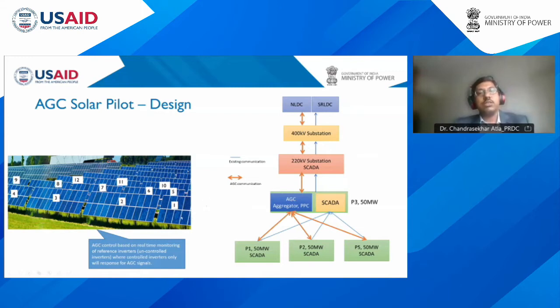the philosophy we made here is by imagining that each solar panel is connected to a 1 megawatt inverter. So identify the inverters in each block and make a couple of inverters reference inverters, maybe 10-20% of the inverters as reference. That means you are not going to control those inverters; those will act as a reference. The remaining inverters you can control, so that you can quantify how the inverters are responding. Basically in regulation down, especially in critical cases, if you operate the plant lower than the availability, then you can think about regulation up also. But in this pilot, we are mostly concentrating on regulation down activity, and regulation up is just one use case to check how it happens. So this is the philosophy we adopted, and the commissioning is completed now.